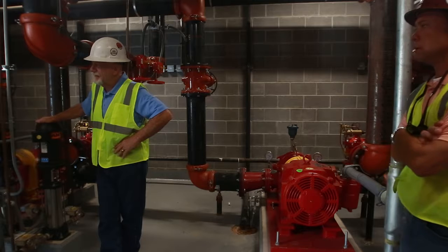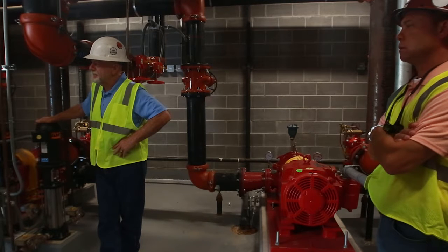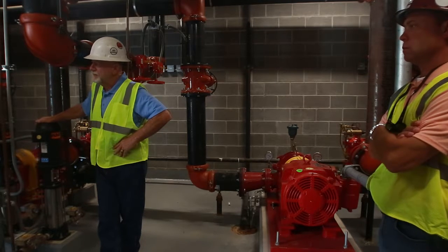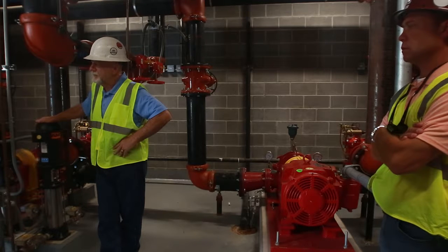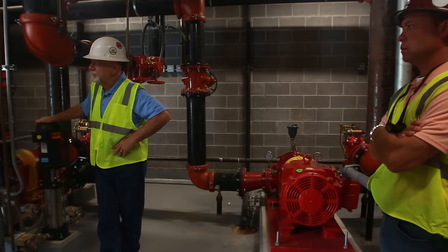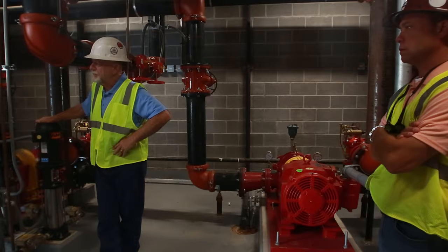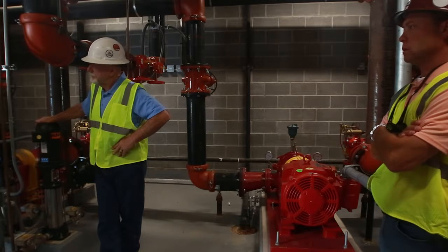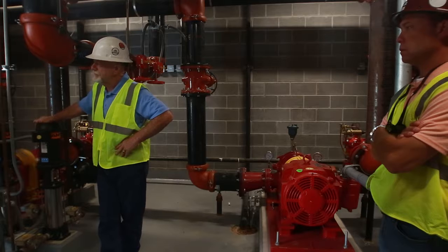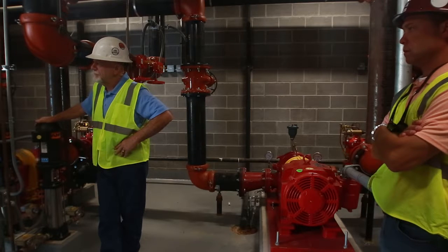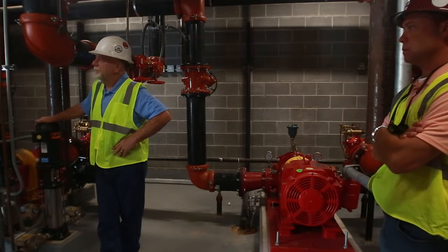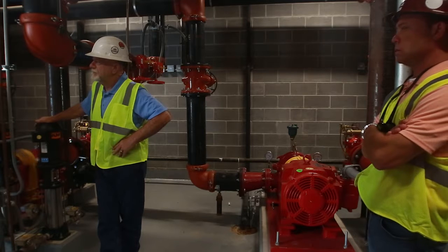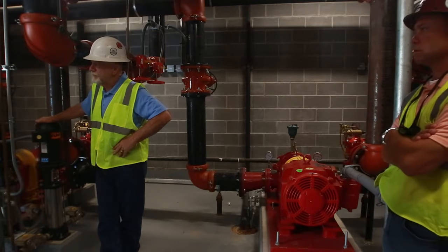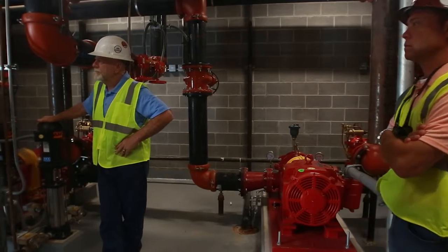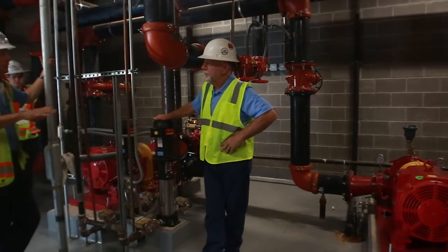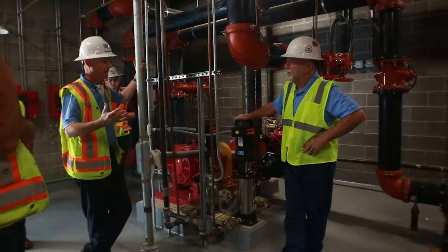Well, what we see over there is on our pressure gauge on the controller, if it is not above 155, we start that pump, it starts ramping up. If it's below 150, it comes on hard, wide open. If it's between 150 and 155, it comes on and starts ramping up till it makes 155, then it'll start backing off. And for testing, it's kind of difficult. What we've been doing is turning the jockey pump on, making it 155 or better, testing, it comes on at a low speed and just sits there and runs at a low speed for 10 minutes. And then we shut it off.